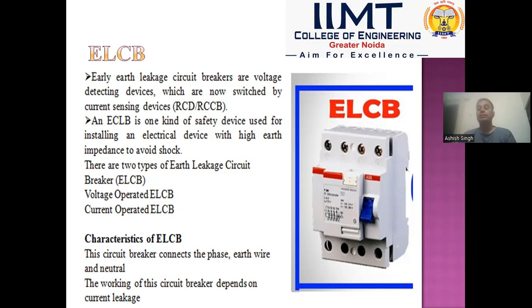Under normal condition, when no current leaks through earth, the incoming current coming to the device from the phase wire is equal to the outgoing or return current that exits from the apparatus through the neutral wire. And so no current is flowing through the relay wire and ELCB does not operate.